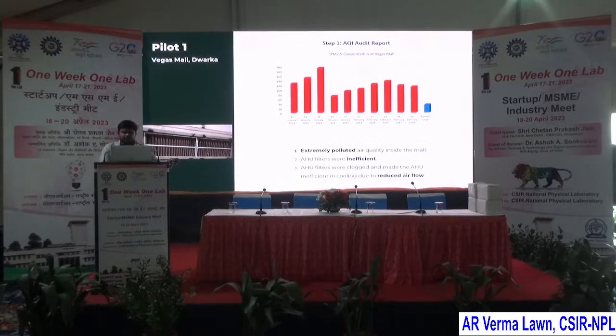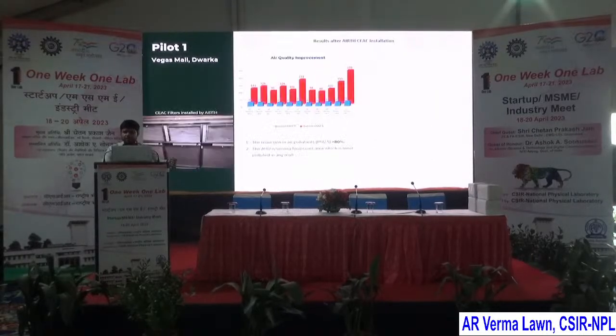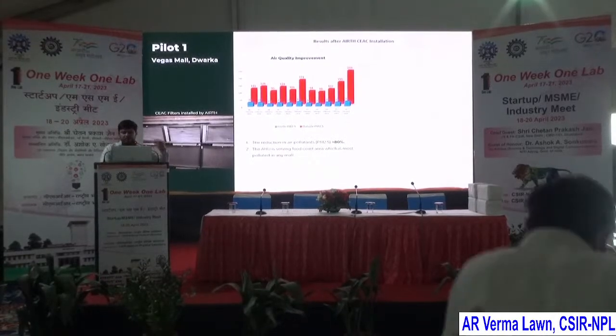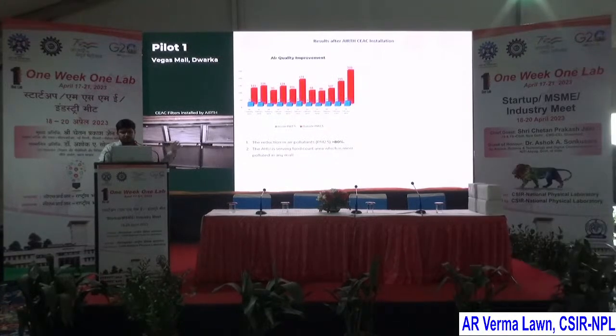This is a pilot that we have done in one of the malls in Delhi, Vegas Mall, Dwarka. It has an inefficient system. We did an AQI audit and energy efficiency audit, figured out that the AQI readings were really high, the air pollution levels were extremely bad, and the airflow through their AHU or the air handling unit is really low, even lower than the designed CFM. What we then did, we installed our system. What we were able to see two things. One, the air quality improvement. We compared outside to what's the AQI inside. As you can see, the red bar graphs are what is outside, and with blue is something that we were able to achieve with our system.